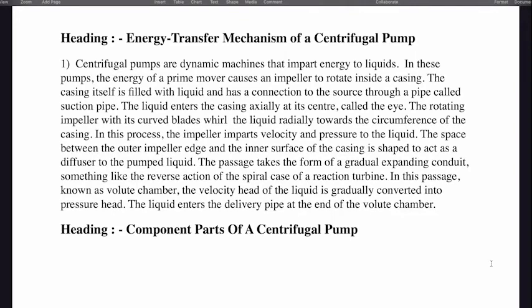Energy transfer mechanism of a centrifugal pump. Centrifugal pumps are dynamic machines that impart energy to liquids. The energy of a prime mover causes an impeller to rotate inside a casing. The casing is filled with liquid and has a connection to the source through a pipe called the suction pipe. The liquid enters the casing axially at its center called the eye. The rotating impeller with its curved blades whirl the liquid radially towards the circumference of the casing.